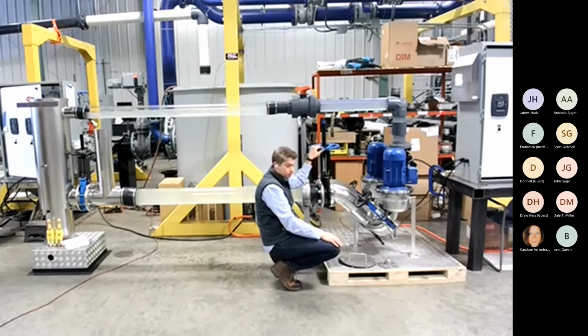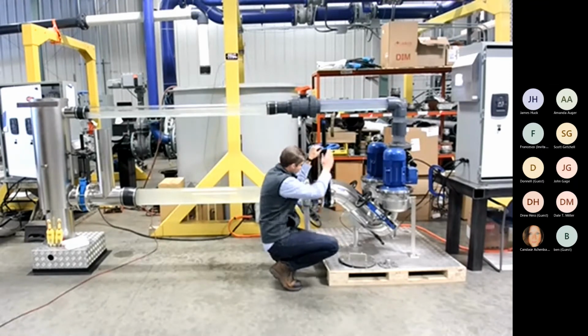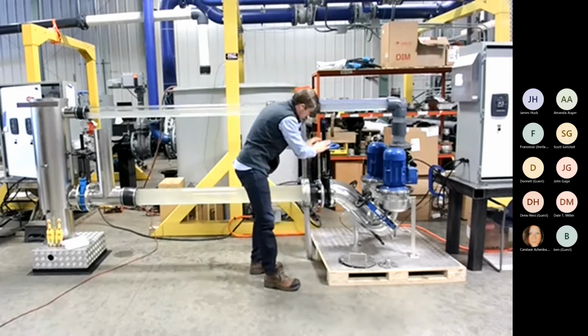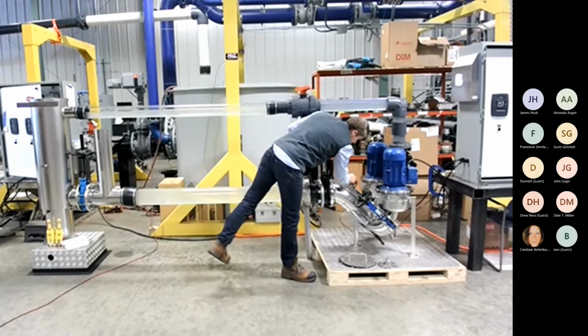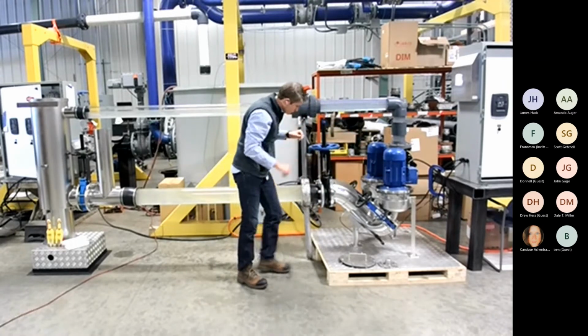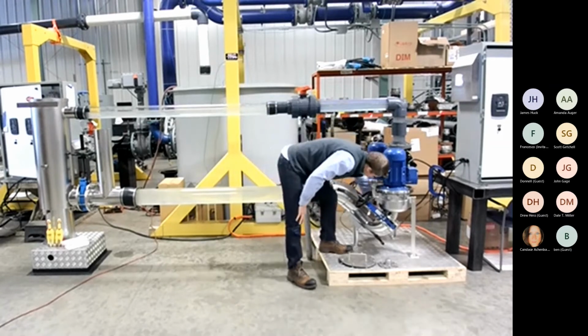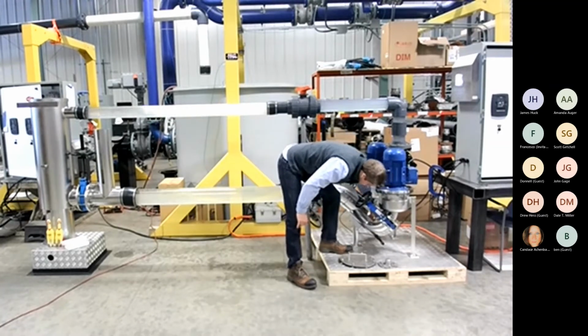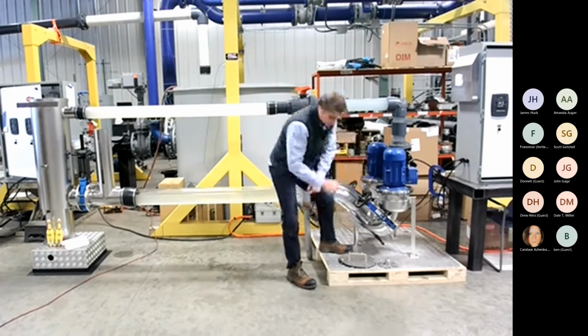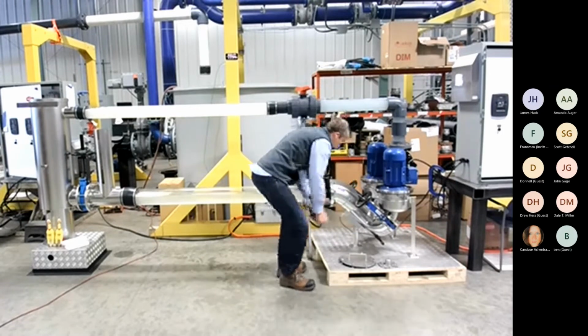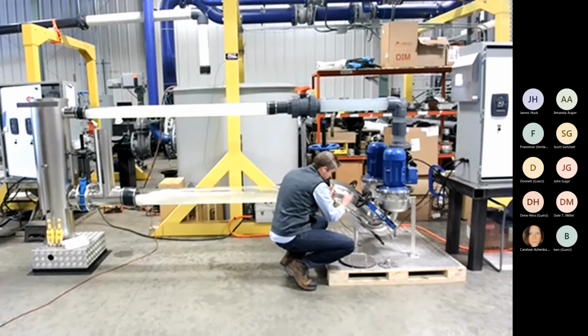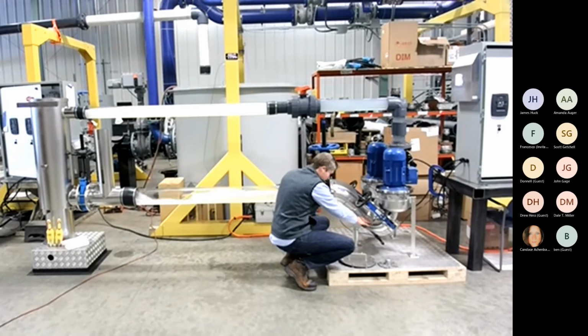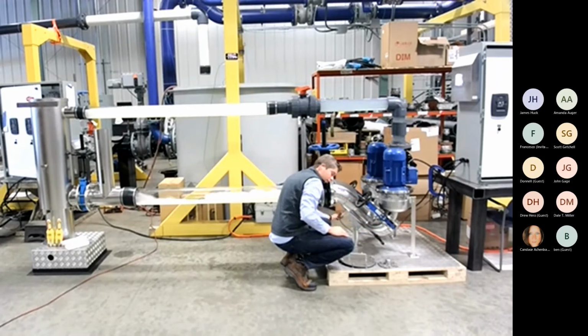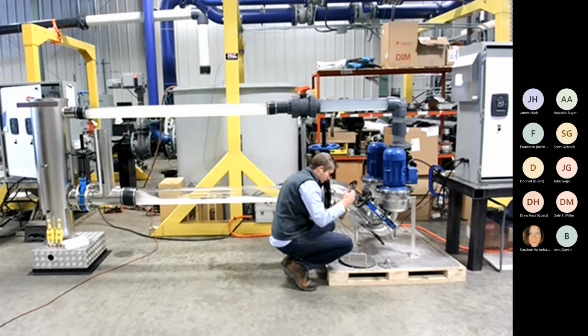What we'd have to do is close this main isolation valve right here, and close both of these isolation valves for the motors. Down here in the bottom is a strainer trap clean out and a ball valve. So I'm going to open up that ball valve and just dewater this part of the pump, right? There's 3 gallons or so in this section of the pump. And now I can freely remove this level sensor and replace it, repair it, clean it, whatever you need to do.